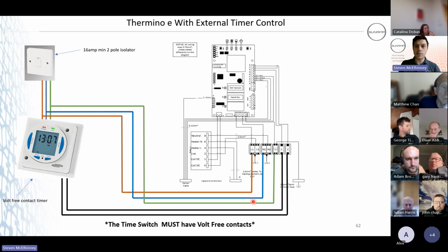Thermino E with an external timer control. This is a volt-free contact timer because, you would wire the control circuit for that into terminals 1 and 2. So terminals 1 and 2 is a volt-free circuit. So you need a volt-free contact timer. So don't apply power in here, otherwise the board will just explode.